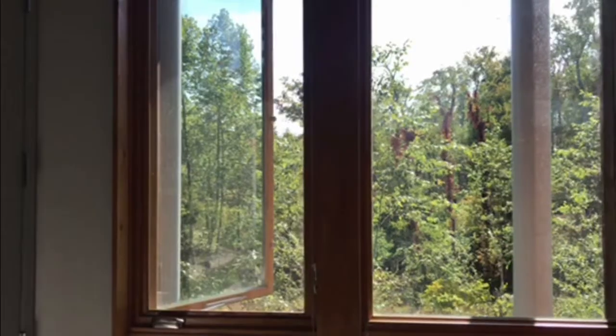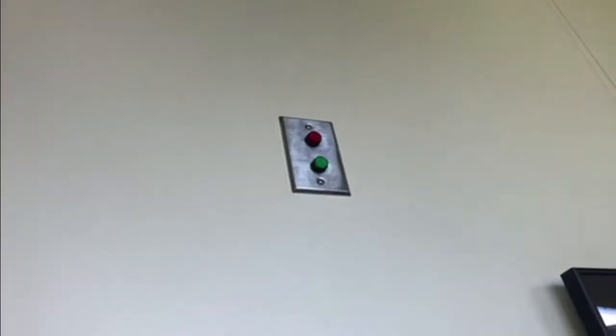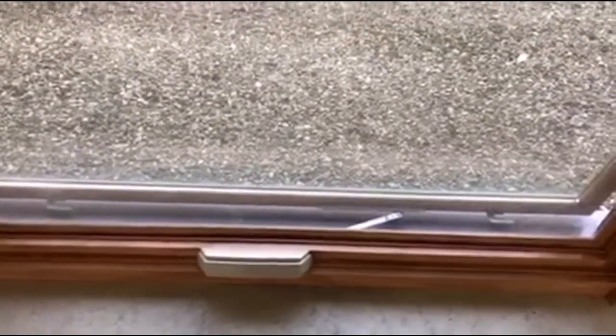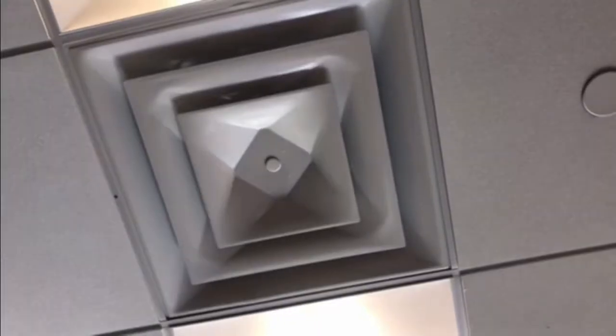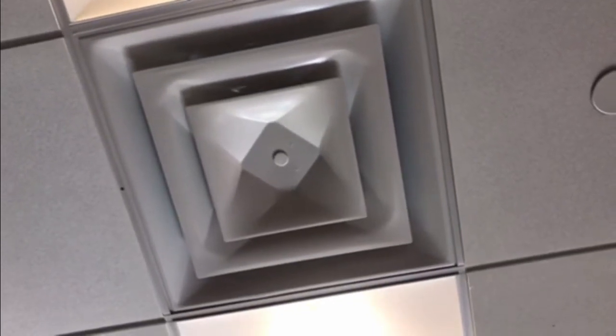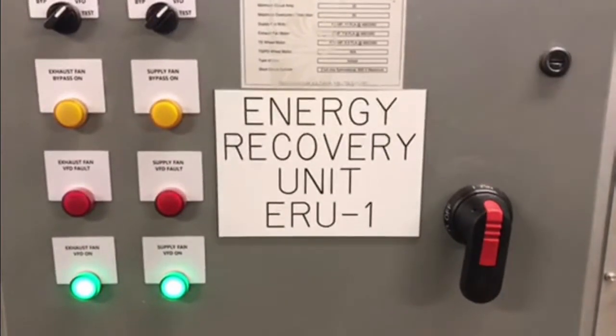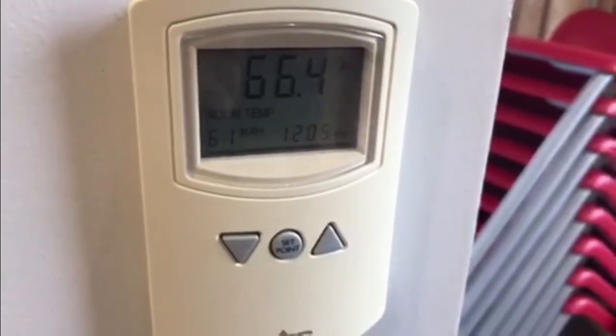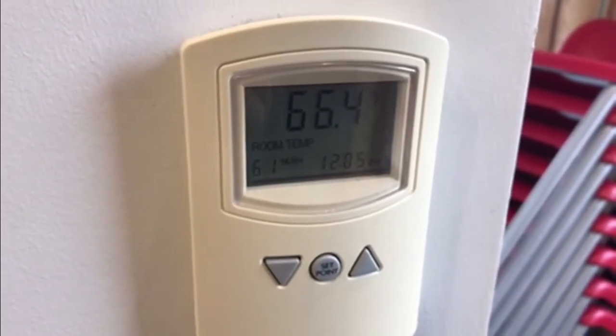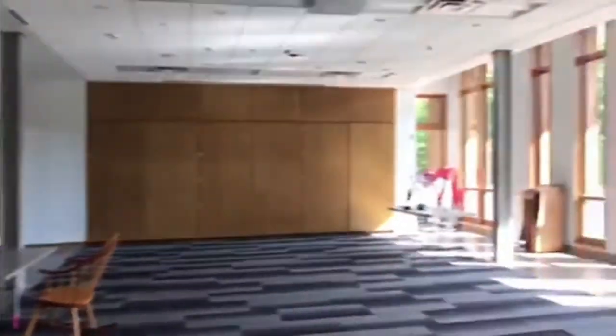There is also a three-phase cooling system. The first phase is passive natural, where windows can be opened because the outdoor temperature and humidity are suitable, normally between 60 and 80 degrees Fahrenheit. A green light system indicates to occupants to open a window, which triggers automatic windows throughout the building. The second phase is active natural: open windows are okay, but additional air exchange is needed because CO2 is high, so a mechanical fan turns on automatically. The third phase is mechanical with energy recovery, used when outdoor conditions are not suitable for natural ventilation, essentially acting as a conventional HVAC system but with an energy recovery unit in the basement that reuses heat in the winter or acts as a heat sink in the summer. At night, the building flushes by taking outside air in and allowing hot air to escape via high locations to pre-condition the building. There are 11 different zones, each of which can be individually heated and cooled, keeping energy from being wasted on empty rooms.